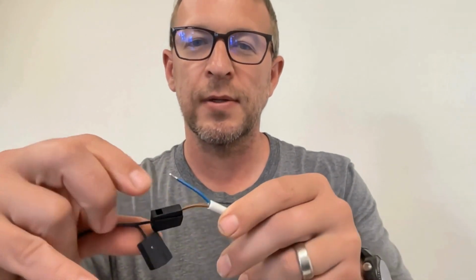This is a very corrosion resistant part. Well, if it does sit in water, you can get water wicking into the wires, which will corrode the wires, but the wires are actually tinned the full length. They're as corrosion resistant as wiring can possibly get. And this is just a very simple push-in connection and should be easily serviced as needed if you need to replace it, but that's how they work.